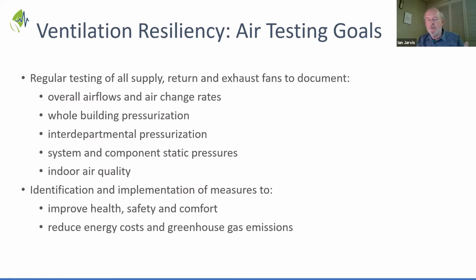You can speak to that with confidence because it's been measured, and the converse applies: if you haven't had your systems tested recently, there is no way that you can speak with confidence that you're meeting the standards that are required. So the starting point is, have we got the right amount of air? The second point is the whole building pressurization, and we'll show you some interesting examples where if your supply volume is down and your return volume and exhaust volume stay the same, guess what? The building goes negative, and that's where you get the howling drafts at the main entrance. And the converse can apply as well. You end up with the building being overpressurized, which is very expensive from a utility cost standpoint, but also is equally unpredictable and uncomfortable for users.